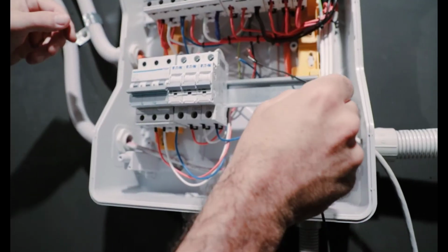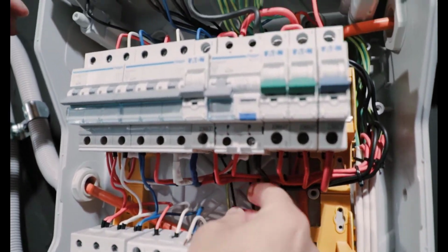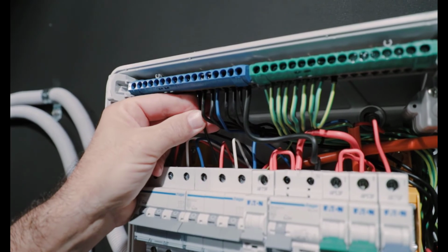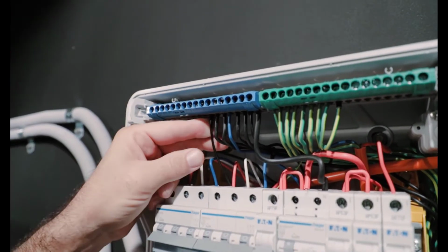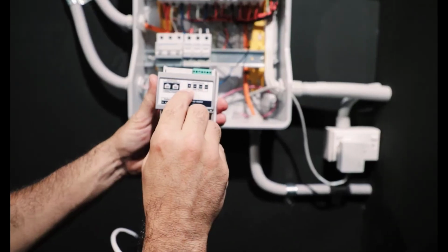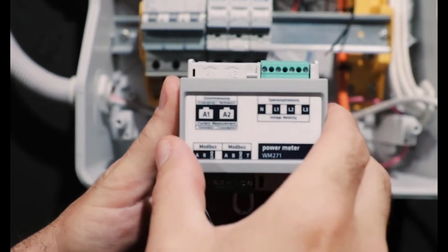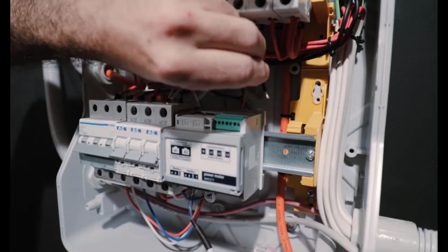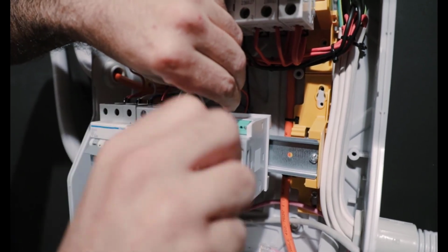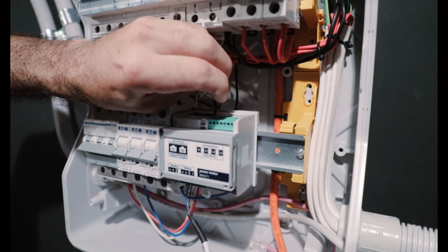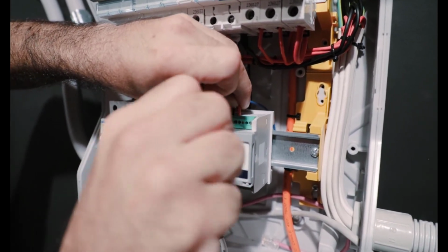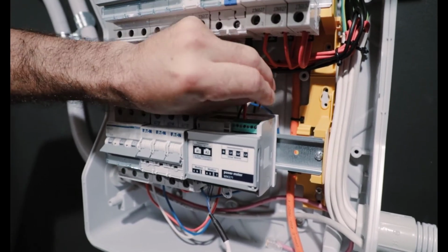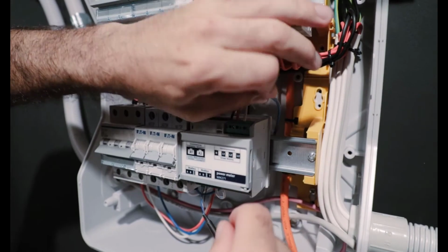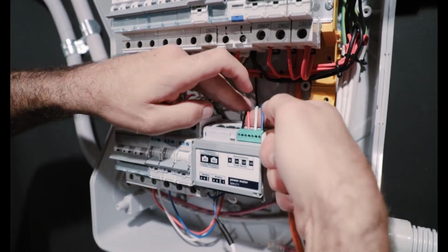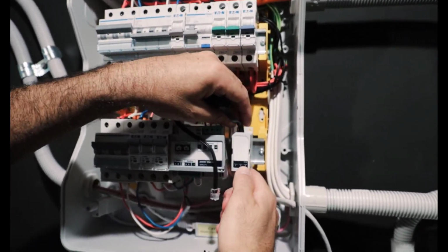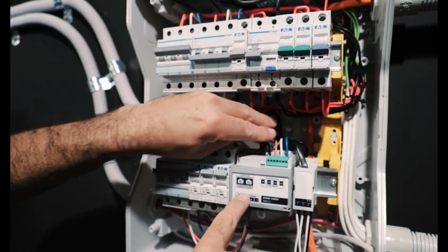So now all that description's over, you can see that the main three-phase latched isolator for the sonnen system is in, as well as the three separate MCBs for the meter, which have now been nicely wired in. Neutral just going in. Now what you probably also notice with all these videos is that the meter doesn't require an earth. That's because it's a separated extra low voltage meter, so no earth required, just the neutral, L1, L2, L3 on a three-phase system, or just obviously a single active on the single phase. So once more, neutral goes in, L1, L2 and L3. And our CT set goes in, transducer, plug this one straight into A2.